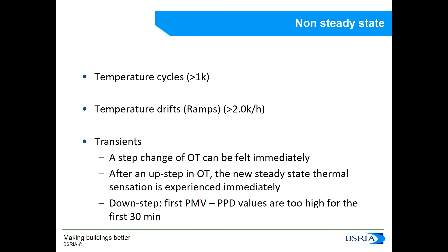These calculations refer to steady state conditions, but in a real building there are temperature variations due to, for example, the influence of controls. We can have three types of non-steady state conditions: temperature cycles, temperature drifts or ramps, and transients. Temperature cycles can occur due to the control of temperature in a space, and if the peak variation is less than one degree, the standard thermal comfort calculations can still be used. With temperature drifts or ramps, if the rate of temperature change is lower than two degrees per hour, we can still use these methods.